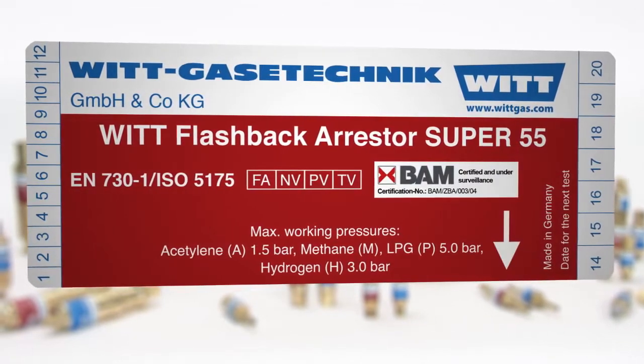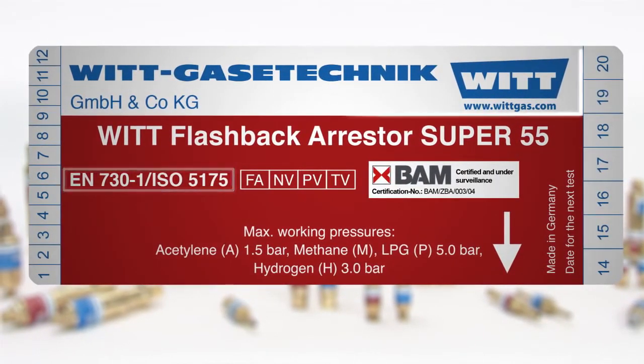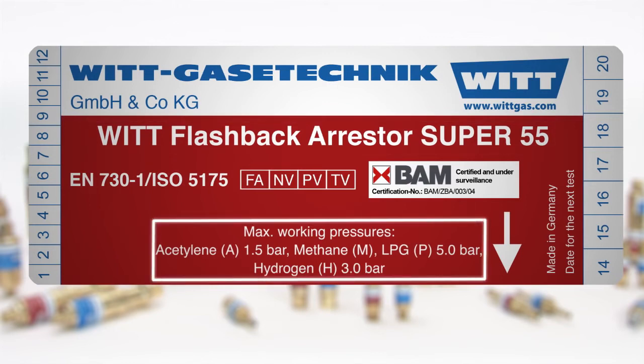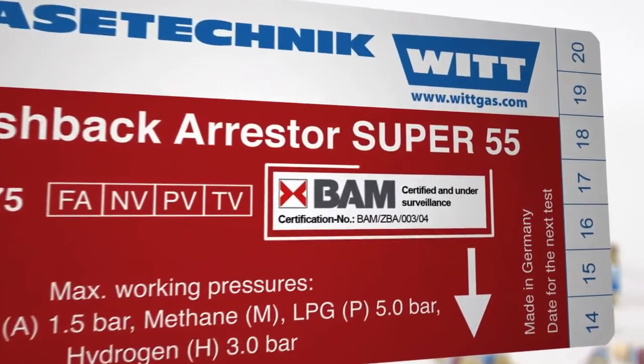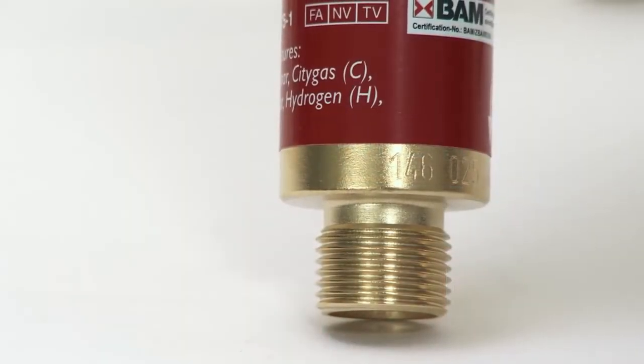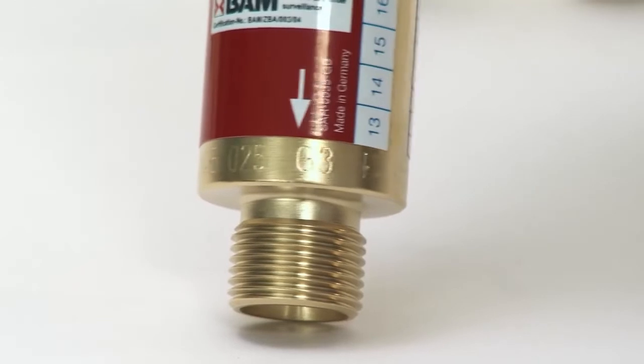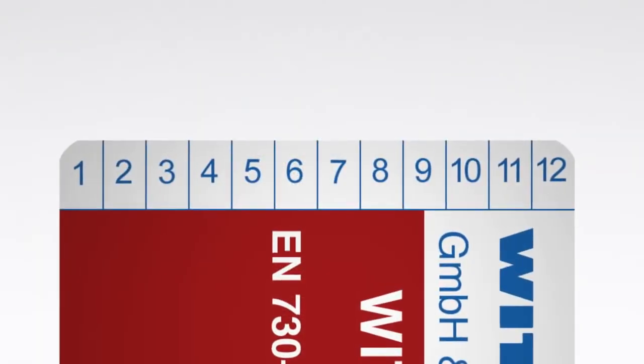Safety begins with the product label. For example, flashback arrestors according to EN 730 Part 1 must be labelled with the following information. The certification number of an external test body provides certainty that compliance with the standard has been inspected by an independent authority. For complete traceability of every individual device, the article number, date of manufacture, and serial number are engraved by WITT. The labels also provide practical marking options to note the date of the next test directly on the device.